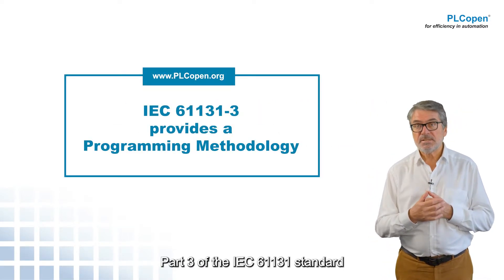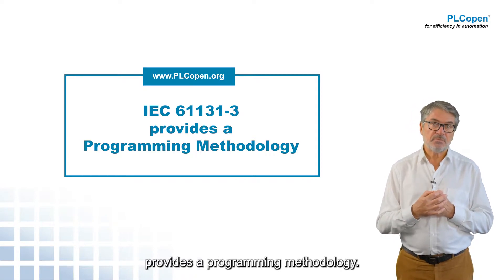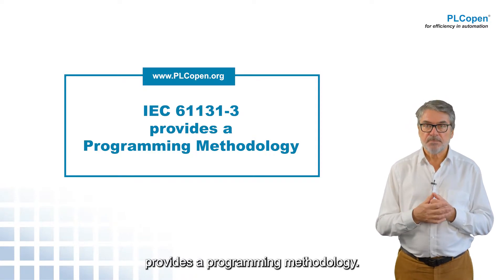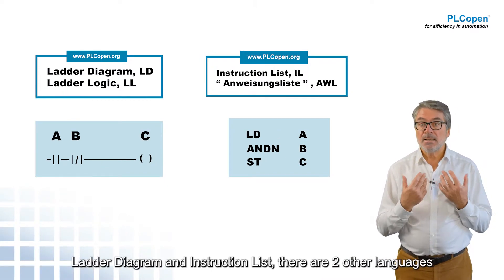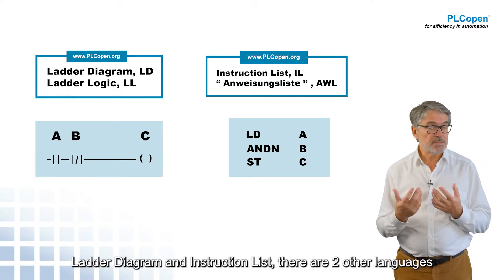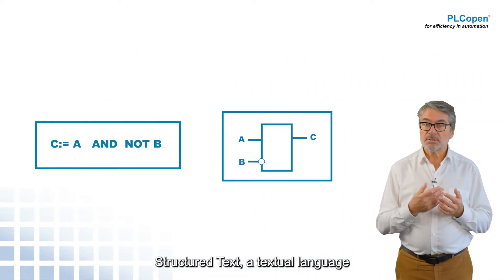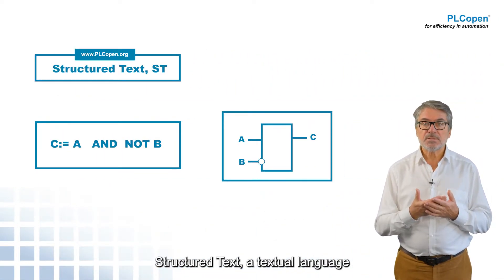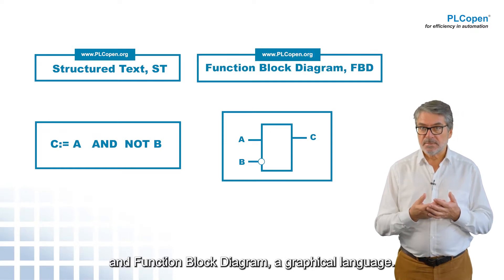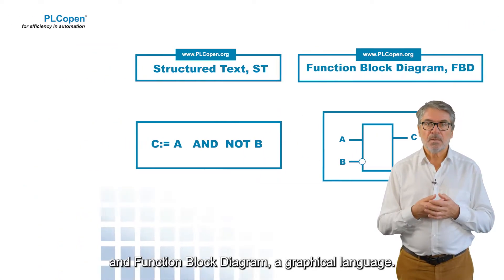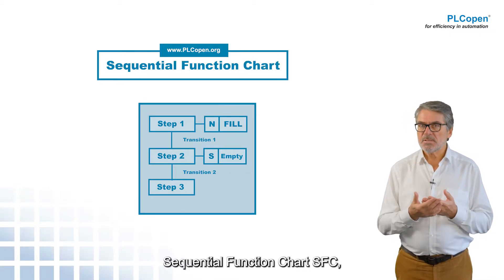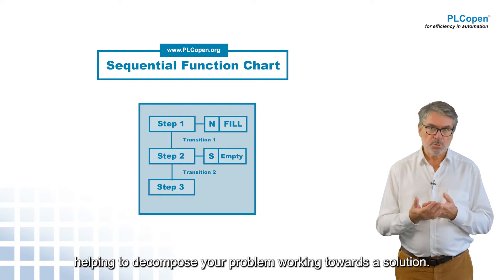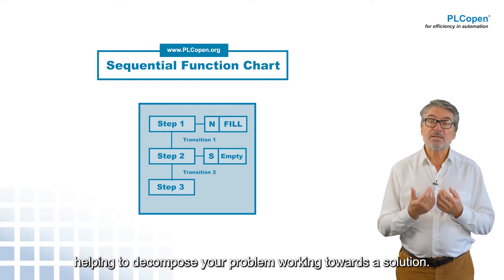Part 3 of the IEC 61131 standard provides a programming methodology. Apart from Ladder Diagram and Instruction List, there are two other languages: Structured Text, a textual language, and Function Block Diagram, a graphical language. And on top of that there is a structuring tool defined — Sequential Function Chart, SFC — which helps you to decompose your problem working towards a solution.